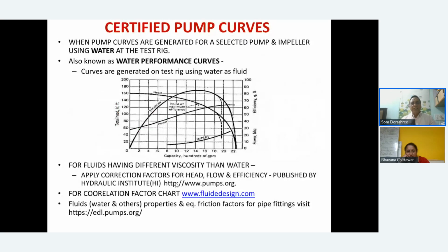Now, what is a certified curve? As I told you, when you ask the manufacturer to give you a certified curve, he will take that specific pump, put it on their test rig, and plot the curve. They keep increasing the flow and throttling the valve so that the head changes and the flow changes. Accordingly, they keep plotting the points and give you a curve. This curve also gives the power requirement. So power, flow, and head they will give you. NPSH, how it is calculated, I'll tell you a little later. Wait for a while till we come to NPSH. But this is how the certified curves are made.